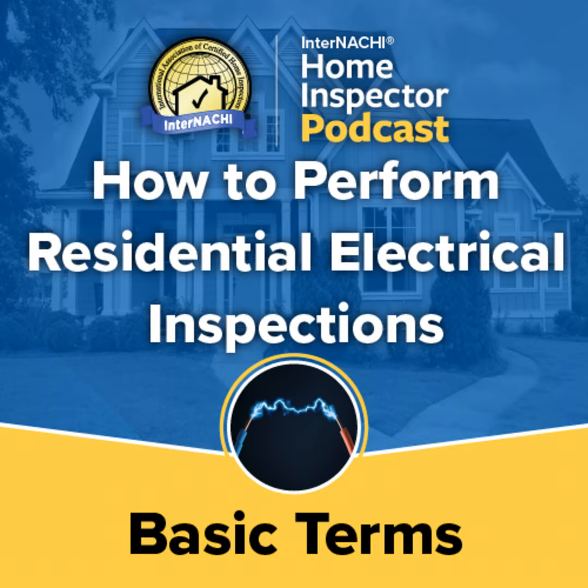The common term neutral wire is more formally referred to as a grounded conductor. A panel ground wire is more formally referred to as grounding electrode conductor, or GEC. A grounding wire is formally referred to as equipment grounding conductor, or EGC. A grounding rod is more formally referred to as a grounding electrode.